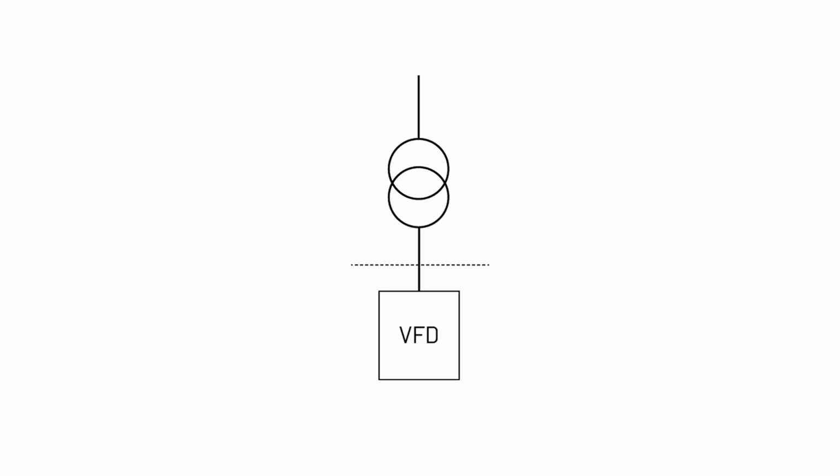The transformer is feeding your load and the load is producing harmonics. The harmonic orders, if we have a three-phase load, will be the 5, 7, 11, 13 and so forth. The six pulse harmonics, which you can say are equivalent to 6 times n plus minus 1. So for 6 plus minus 1, we get 5 and 7. 6 times 2 plus minus 1, we get 11 and 13, and so forth.